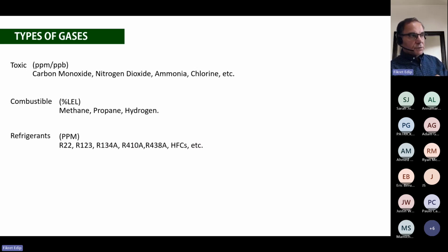Okay. The other one is refrigerants. Refrigerants are measured in ppm in general. Some of the refrigerants you see on the screen are obsolete because of the Kyoto Protocol, because of the environmental impact. And quite frankly, as you may all know, you guys are in the HVAC industry, the R value keeps changing. A new one being added, the older one being phased out because of the environmental impact. But my goal here is to show you that these gases fall into the same category where, as a gas detection system designer or manufacturer, we need to have sensors that can detect those gases. Again, it is measured in ppm, and also ammonia. Ammonia fits into the same category, refrigerant, as well as CO2. Now they started using, as you may be aware, CO2 as a refrigerant.